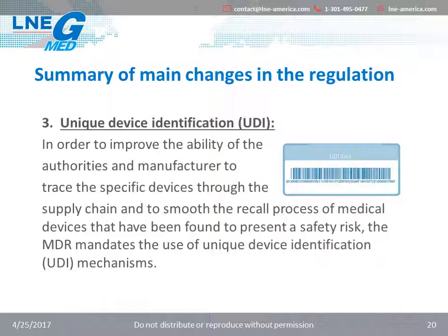The MDR mandates the use of unique device identification UDI mechanisms. The traceability of devices by means of a unique device identification system based on international guidance should significantly enhance the effectiveness of the post-market safety related activities for devices, which is owing to improved incident reporting, targeted field safety corrective actions, and better monitoring by competent authorities.